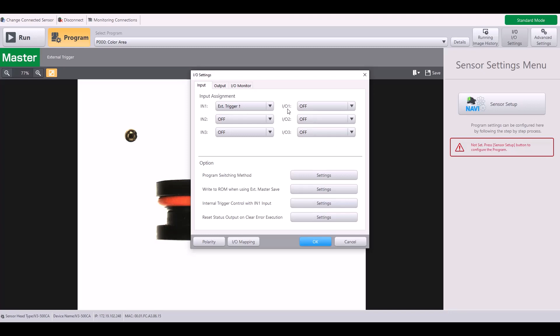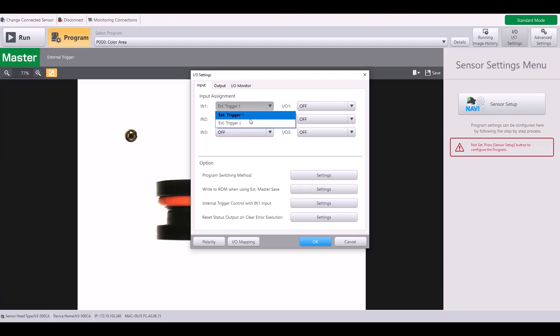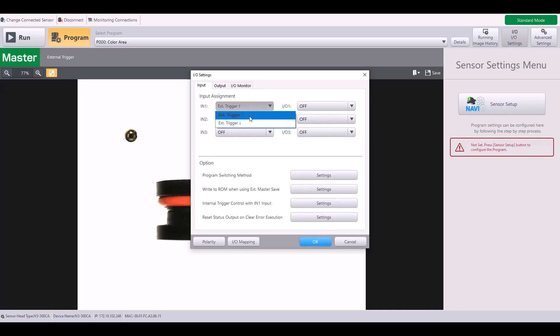So now you can see I have a maximum of six inputs for this self-contained model. And when you hit the dropdown for each input separately, you can see the available functions. For input one, the two functions are external trigger rising or external trigger falling. The default will always be external trigger rising.